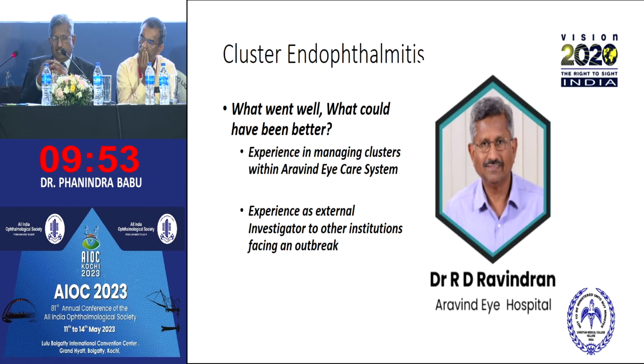And then we really understood that with ETO, as much as the cleaning, the drying is also very important. From that day we decided to dispose of the tubings. We will not do ETO; either we buy tubings that can be autoclaved, or we go for fresh tubing. With ETO you also have to be very careful, because the indicator before and after is very difficult to read to know whether it has been sterilized. Here again we moved towards adding other indicators. Recently, other process indicators for ETO have come, and using those also becomes important.